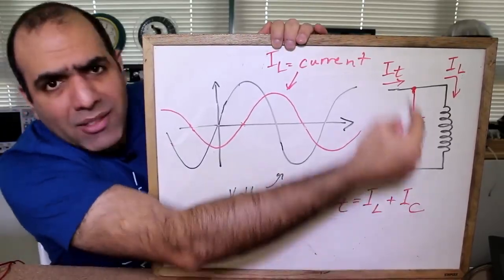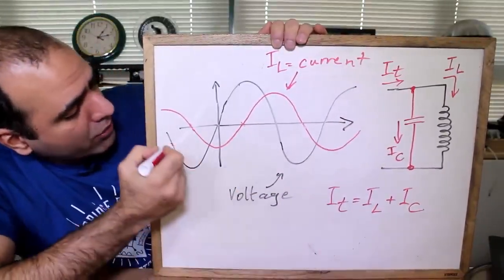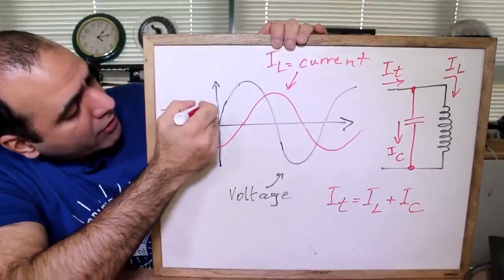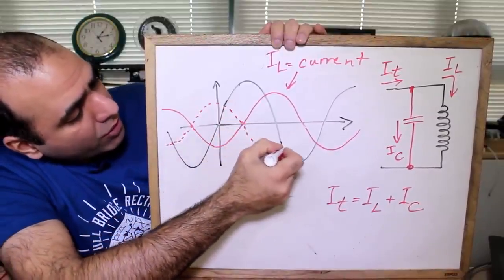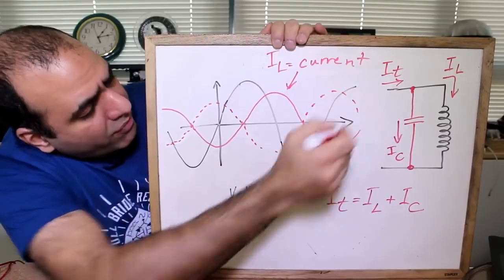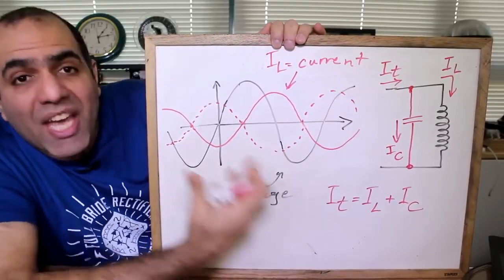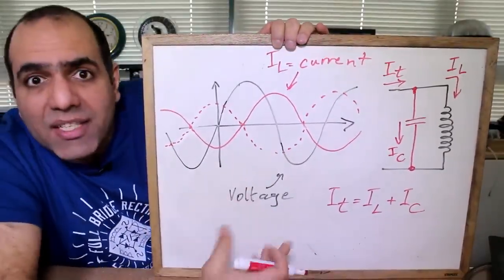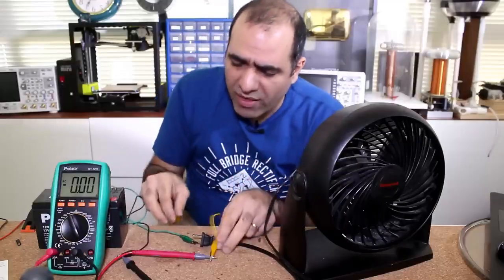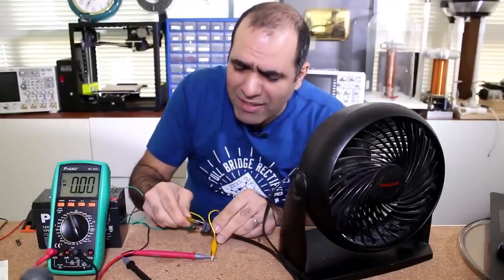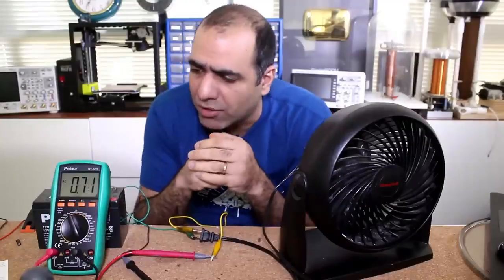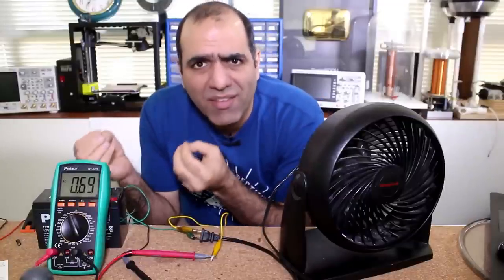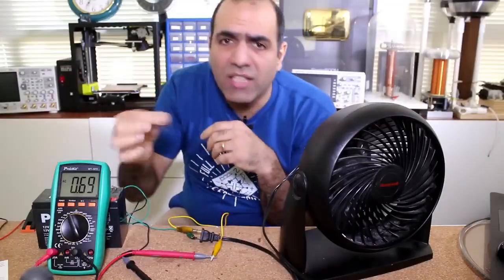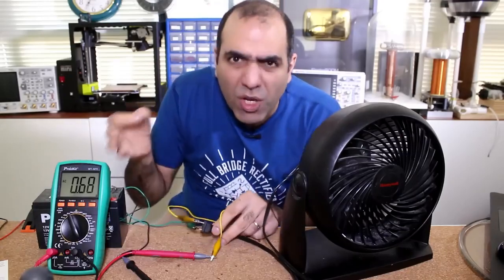So if we add a capacitor parallel to the inductive load, with the peak current equal to the inductor current, 180 degrees out of phase, they add up and cancel each other. Power factor fixed. For example, most fans with AC motors don't have a capacitor in them to correct the power factor. It is drawing 0.7 amps and I have a 10 microfarad capacitor. Watch the current carefully as I connect the capacitor.